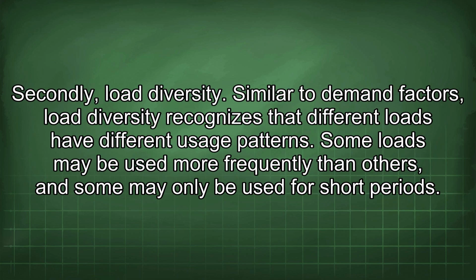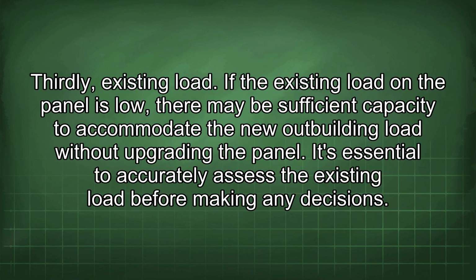Secondly, load diversity. Similar to demand factors, load diversity recognizes that different loads have different usage patterns. Some loads may be used more frequently than others, and some may only be used for short periods. Thirdly, existing load. If the existing load in the panel is low, there may be sufficient capacity to accommodate the new outbuilding load without upgrading the panel. It's essential to accurately assess the existing load before making any decisions.